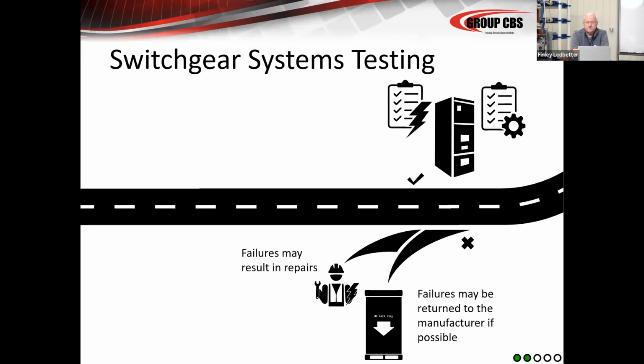Typically, that's what we call acceptance testing. And that's the next segment where we'll go into that deep, but we'll briefly talk about it here where we just say that is where the equipment is tested to make sure that you got your money's worth. You got equipment that will do the job, will operate as specified, as the manufacturer said it would. And that acceptance testing can be done by a NETA certified, qualified, fully accredited member of NETA. It can be done by a non-NETA company to NETA standards. It can be done by a non-NETA qualified quality individual. It can be done by the original manufacturer. It can be done by representatives of the contractor. And as an owner, that's up to you to decide who you want to use. I can assure you there are quality, resourceful individuals in every one of those segments that'll do a good job for you.